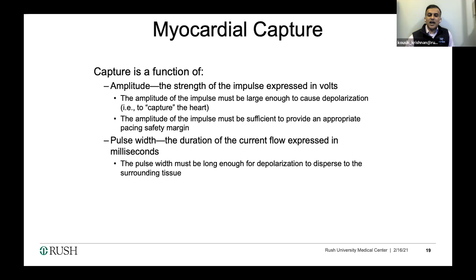So we can achieve capture multiple ways. We can achieve capture at a higher voltage with a shorter pulse width. We can also get capture with a lower voltage and a wider pulse width. And that defines what's called a strength duration curve. So we can test output of a device for capture at multiple pulse widths while keeping the voltage constant, or we can keep the pulse width constant and check it at multiple voltages. And we can create a curve, which is called a strength duration curve, for any patient. And we can then decide what will achieve capture.